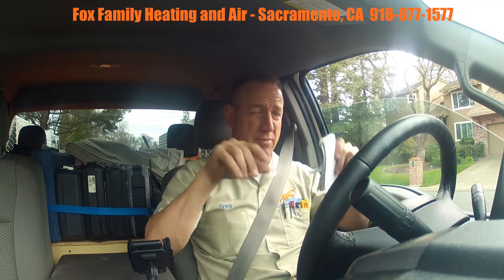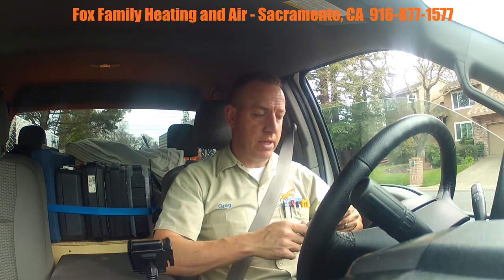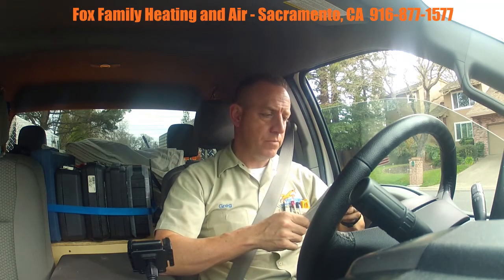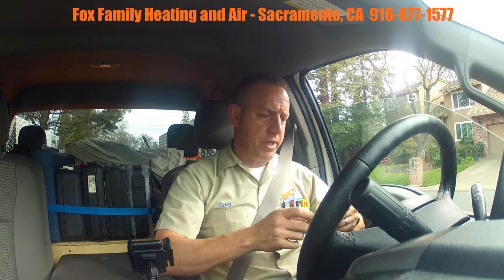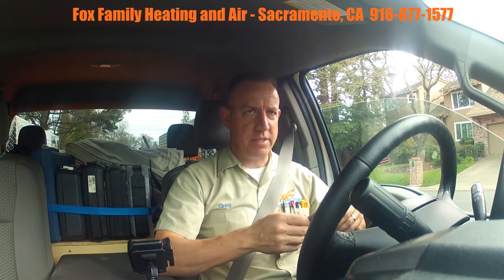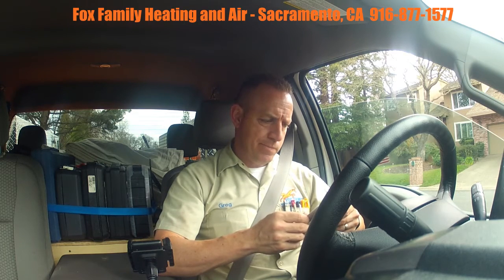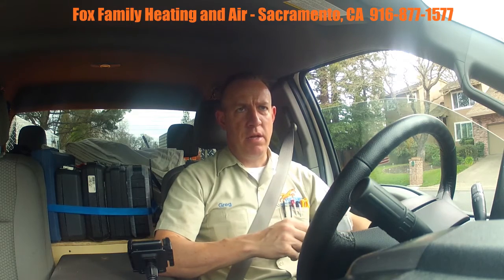I recommended they replace the whole condensate drain line given how wonky everything is run. I'd like to see everything sloping down 100% of the time. I think they're going to move forward with that — they see the priority, especially with AC season coming up.